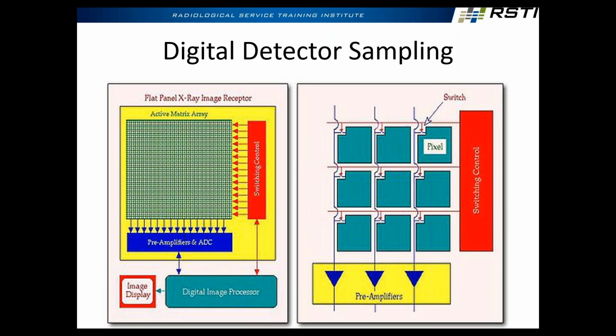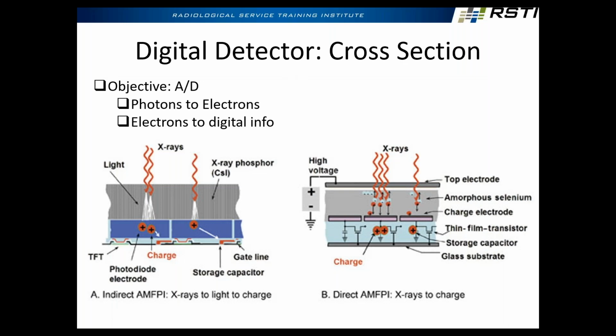So what I'm getting at is there's no repairing these things, right? These are all clean room, under a microscope, built by robots. These detectors go bad. Anyone out there that says they're repairing detectors is not repairing detectors. We at RSTI test and repair parts. We're not fixing the components, they're too small, but there's PCBs in the detector that we can take 2 or 3 detectors that are bad, make one good one. That's being done in the industry, but you're not repairing the stuff. It's too small, you can't even see it. It's all done under a microscope. And these detectors, just like the X-ray tubes, are really, really expensive. Detectors can be 30K on the low end, up to 200K on the high end. So your X-ray tubes and your detectors, those are your 2 big ticket items on any X-ray system, right?